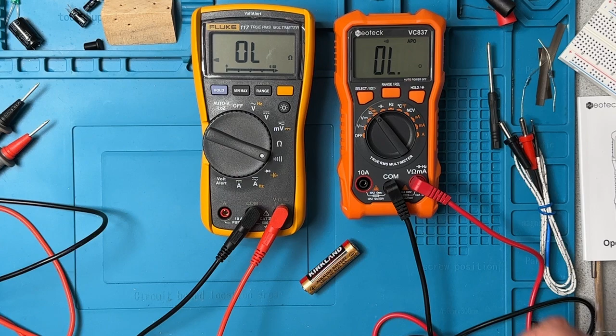It's rated at 47 microfarads. I can tell you from previous tests that it's a little higher than that, but not much. We'll see what the meter says. Capacitors, electrolytic capacitors anyhow, are polarized, so we need to make sure to get the probes onto the right leads here.